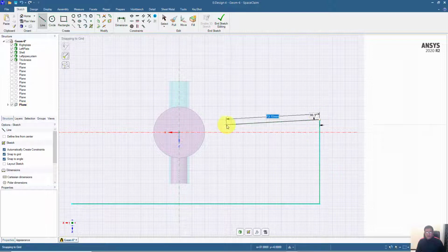So that should be, when we apply the intersection between this plate and the shell side, the height of the baffle should be equal to 30 millimeters, which is equal to 75% of the overall length. So the gap, or the opening, or the cut will be equal to 10 millimeters, which is 10 divided by the 40 millimeter shell diameter, equal to 0.25. So a 25% cut should be there.